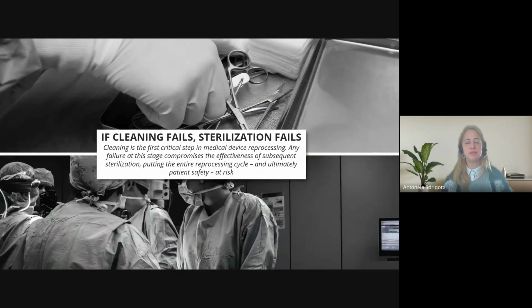So let's start, okay, with the first very well-known sentence, but never a disadvantage to reinforce the concept that cleaning is so important that if it fails, the sterilization will fail. Yeah, cleaning is the first critical step in medical device reprocessing. Any failure at this stage compromises the effectiveness of subsequent sterilization, putting the entire reprocessing cycle and ultimately patient safety at risk.